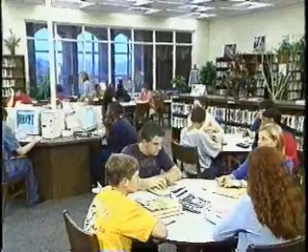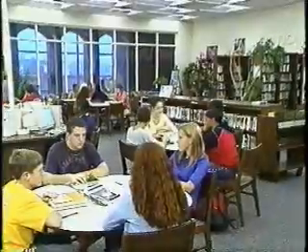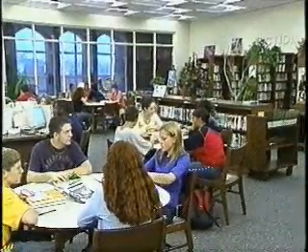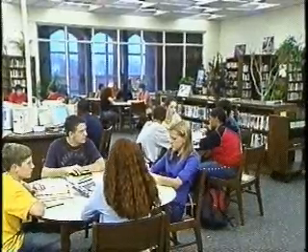My daughter attends school near an Army post where chemical weapons are stored. The school library is overpressurized. How does that work? A pressurized sheltering system draws in and filters extra air so that the air pressure inside a building is slightly higher than that outside. The pressure of this additional clean air blocks contaminated air from seeping in. Pressurized shelters provide a very high level of protection against specific chemicals.